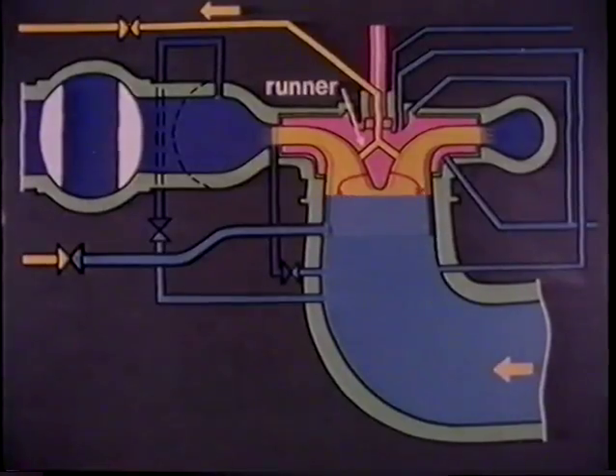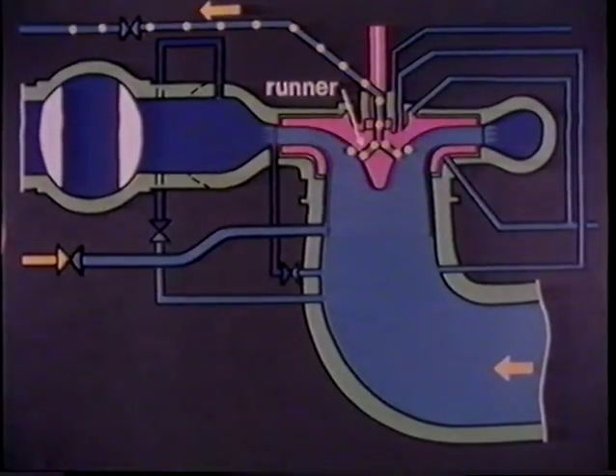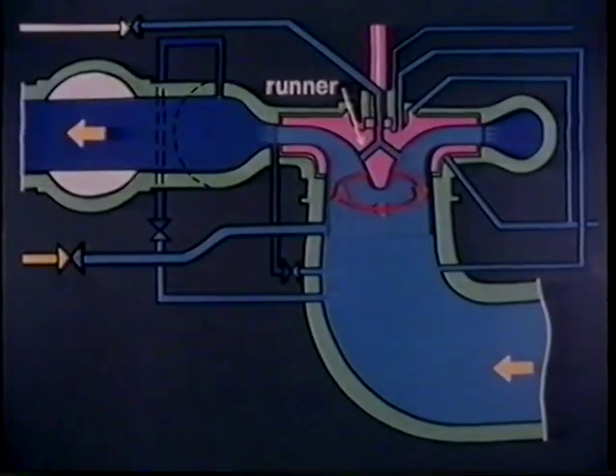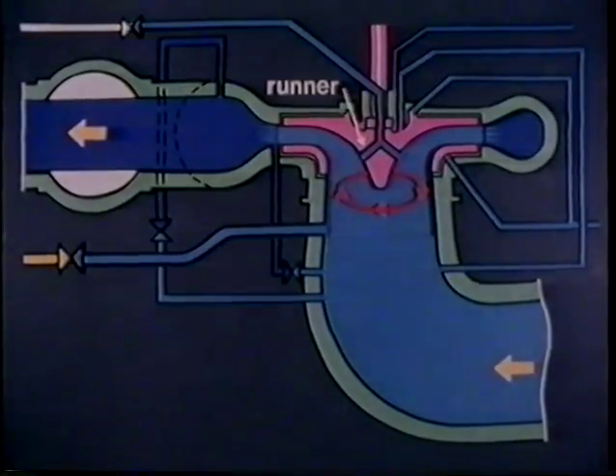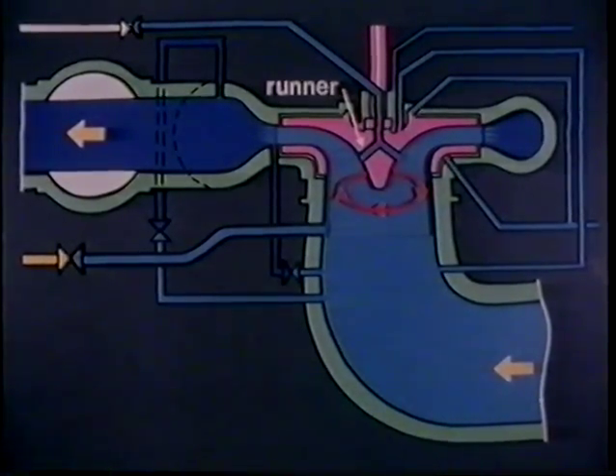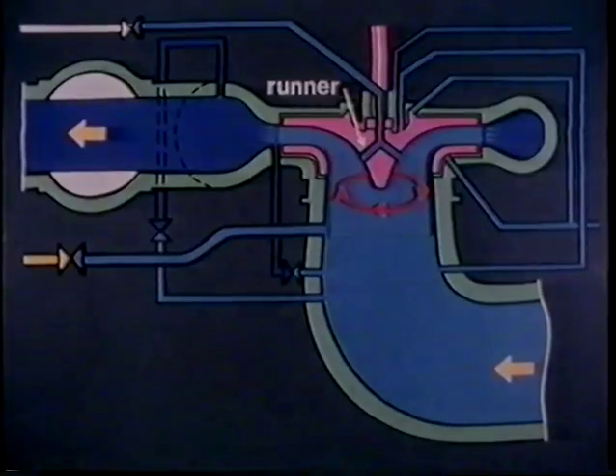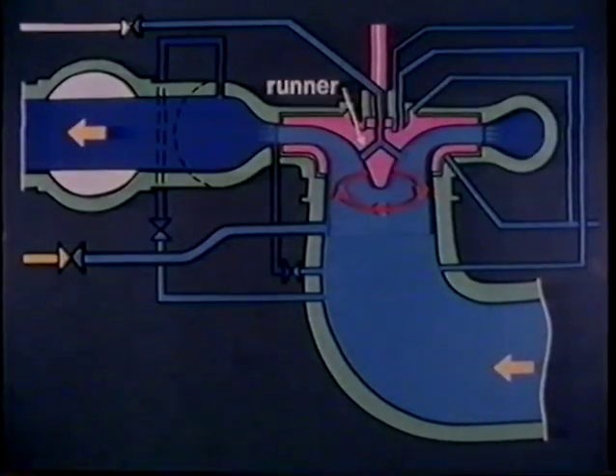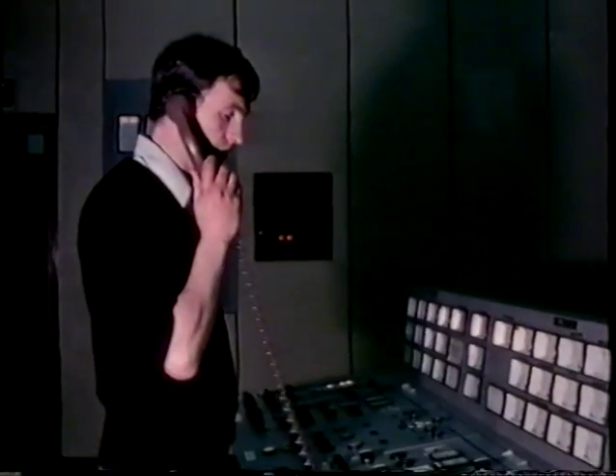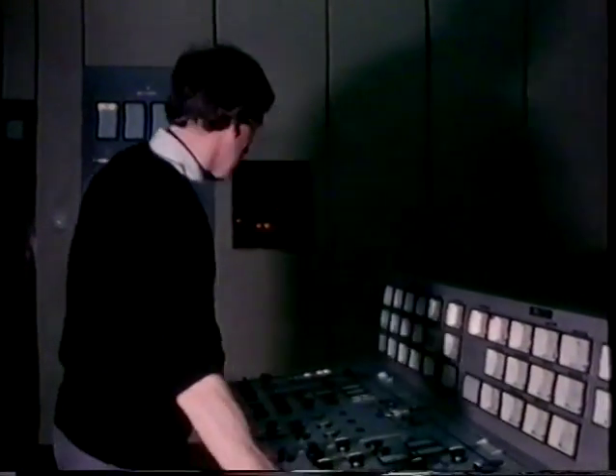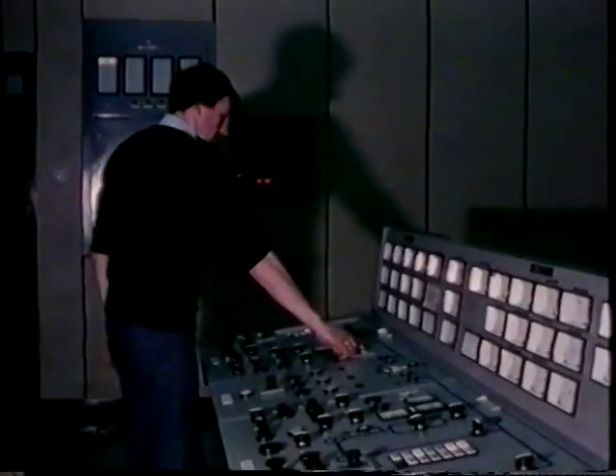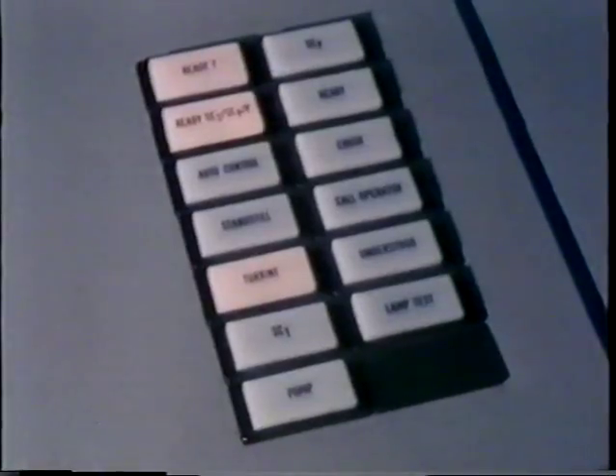From there on, it is controlled by the speed adjusting device in the automatic synchronizer. After synchronizing, water is reintroduced into the runner and pumping begins. The pony motor is switched out and its brushes are automatically lifted to prevent wear. This method of starting up minimizes the electrical impact of bringing a pump onto the system. The normal operation of Turlough Hill from the control room is almost entirely automatic.